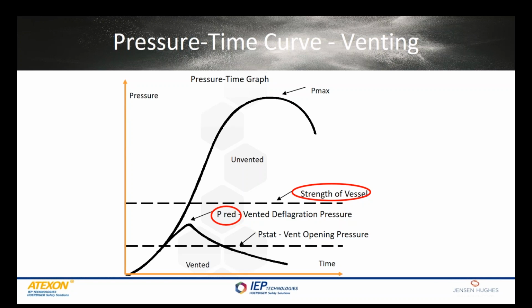P-stat is the opening pressure for the explosion vent. The P-stat is always going to be lower than what the reduced pressure after venting, or P-red, ends up being calculated to. Meaning if you have an explosion vent that you've purchased with your vessel that is rated for opening at 1.5 psi, you cannot have a vessel that's rated for 1.5 psi, because the P-red is always going to be higher than P-stat, because there is a finite time between the opening of that vent and the point at which you're going to get the full effects of that pressure relief. So please keep that in mind, that you must keep the P-red below the vessel strength, and the P-stat is always going to be less than the P-red.